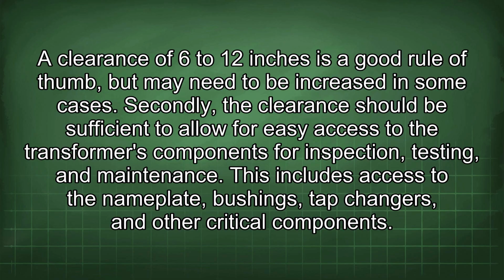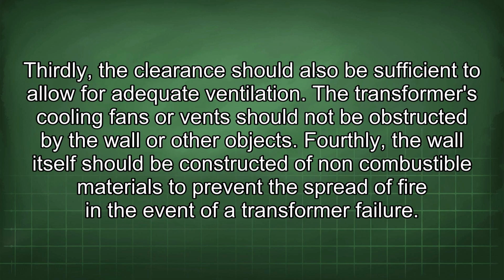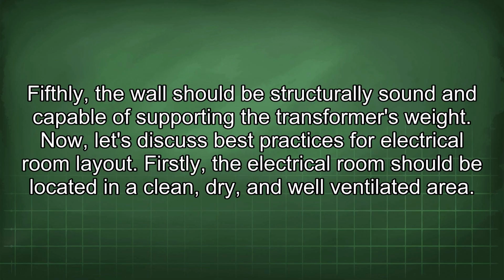Secondly, the clearance should be sufficient to allow for easy access to the transformer's components for inspection, testing, and maintenance. This includes access to the nameplate, bushings, tap changers, and other critical components. Thirdly, the clearance should also be sufficient to allow for adequate ventilation. The transformer's cooling fans or vents should not be obstructed by the wall or other objects. Fourthly, the wall itself should be constructed of non-combustible materials to prevent the spread of fire in the event of a transformer failure. Fifthly, the wall should be structurally sound and capable of supporting the transformer's weight.